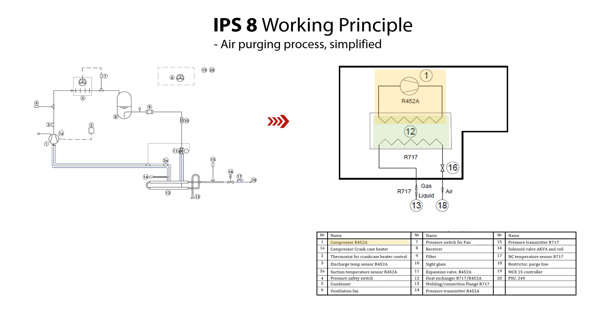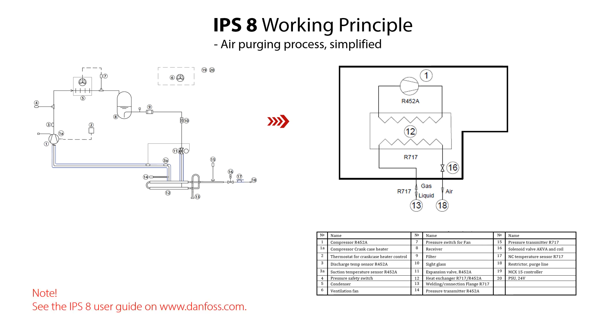When the pressure reaches a predefined upper limit, then the solenoid valve 16 opens. The non-condensable gas is then removed through the restrictor 18. The pressure then increases again and the air purging process repeats itself. You can find more information about the IPS-8 working principle in the user guide.